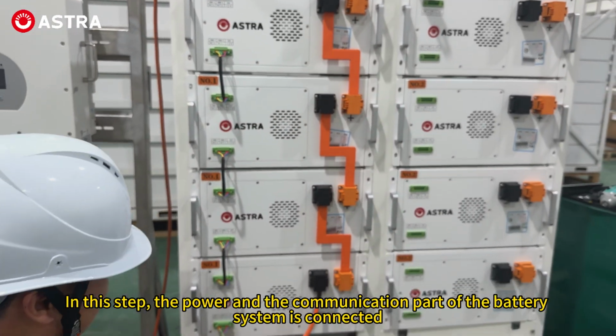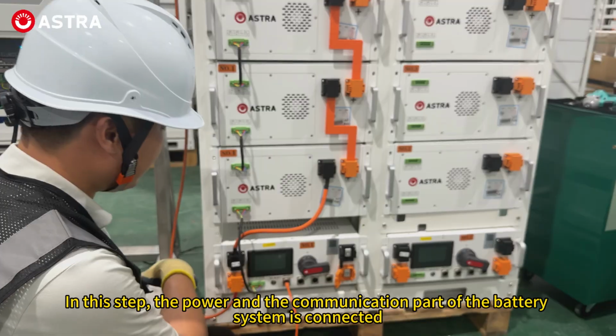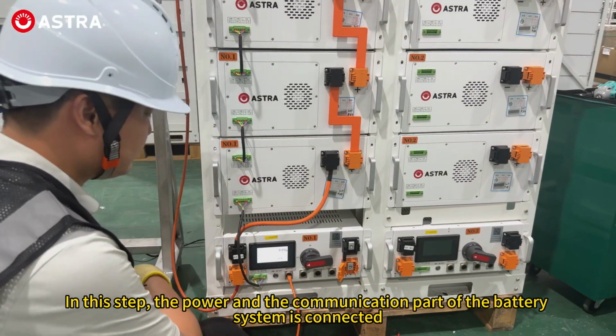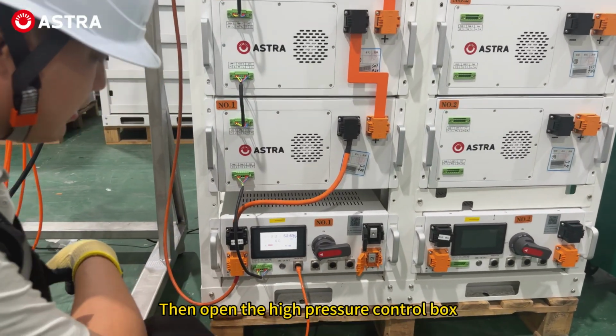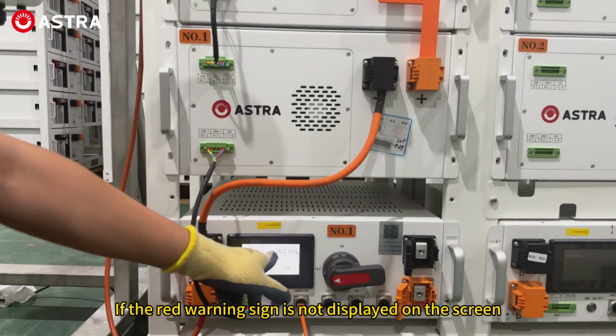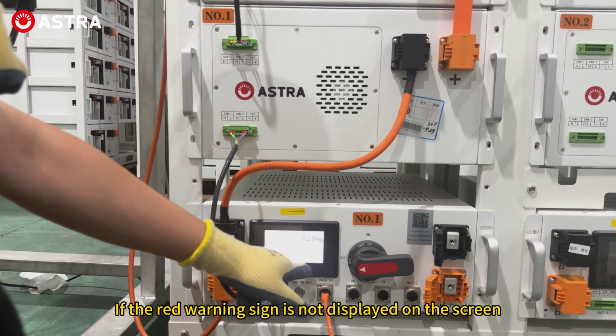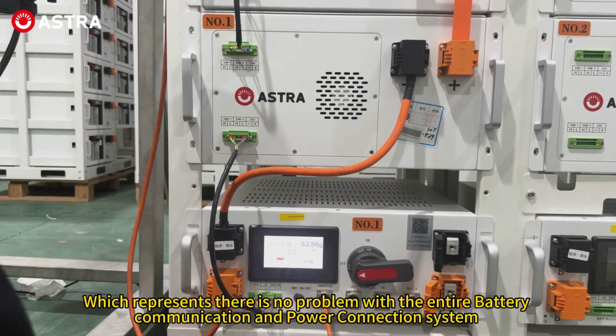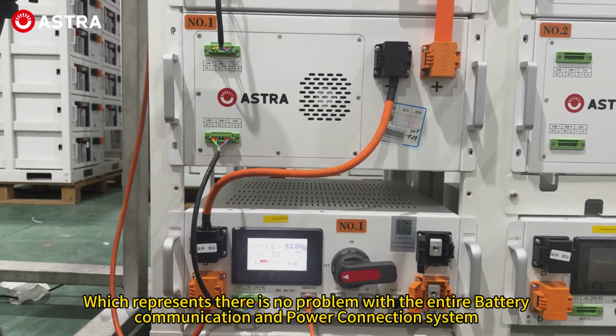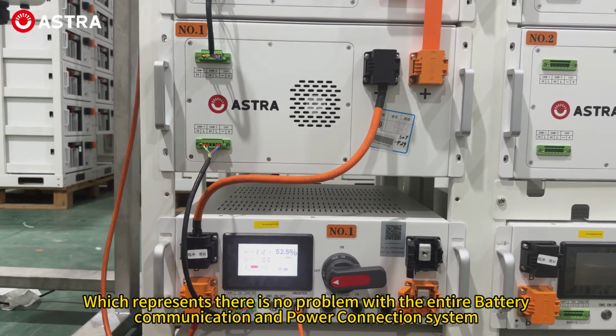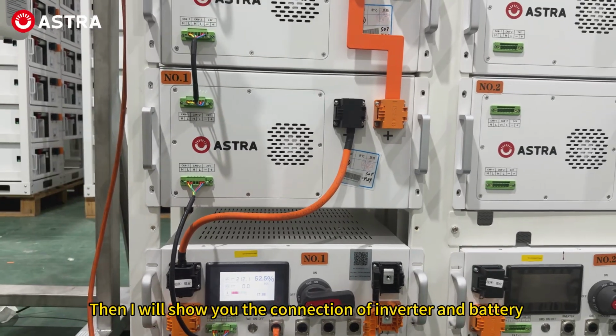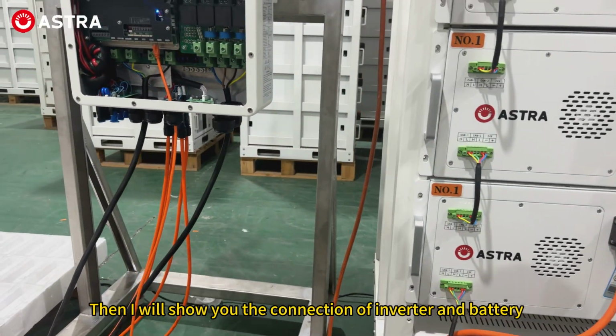In this step, the power and the communication part of the battery system is connected. Then open the high-voltage control box. If the red warning sign is not displayed on the screen, which represents there is no problem with the entire battery communication and power connection system, then I will show you the connection of inverter and battery.